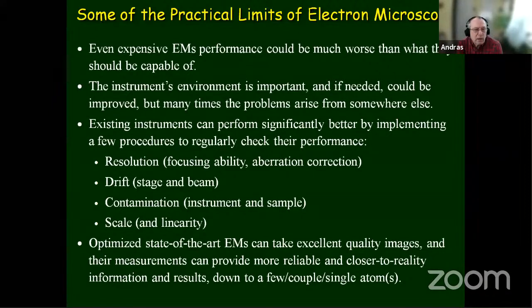One is the focusing ability, including some aberration correction one way or another, choosing the best parameters for a certain task. Take care of the drift, which is both the stage and the beam, meaning the electron beam does not end up at that sub-nanometer spot where we want it to be. Contamination could come from the instrument and the sample, which means material there that we don't want on the surface. We would like to have just the sample and the electrons, and preferably without ultra high vacuum, because that's very expensive, but in some cases we have to do that.